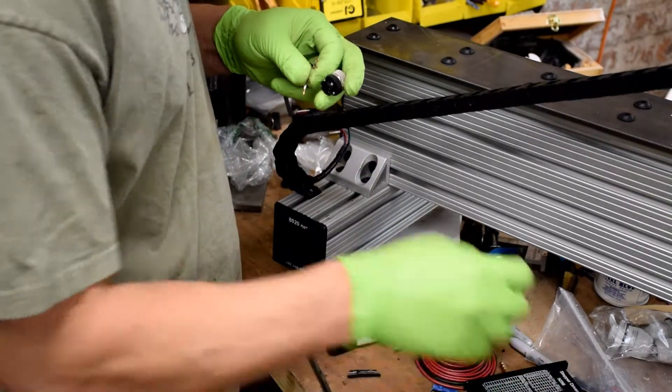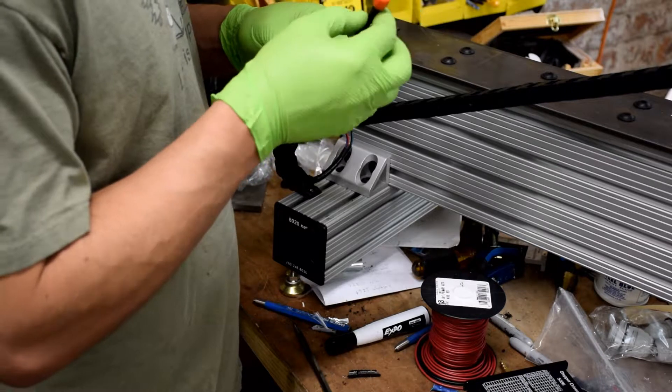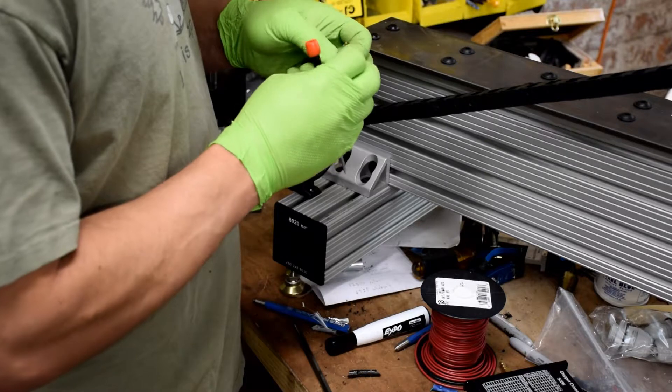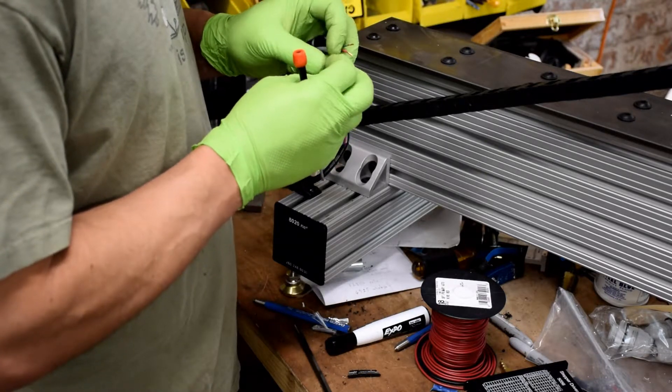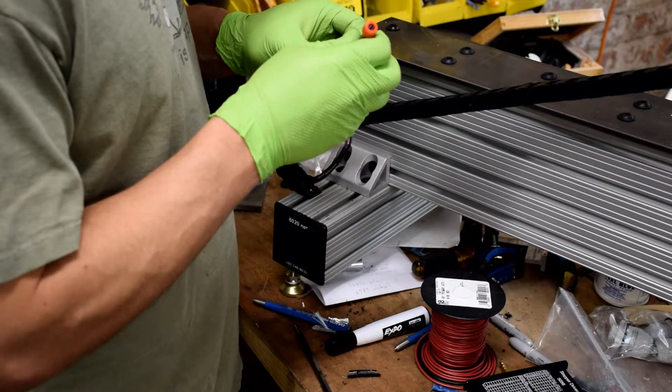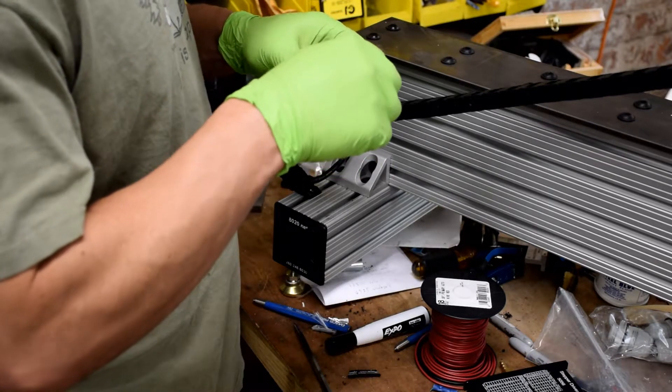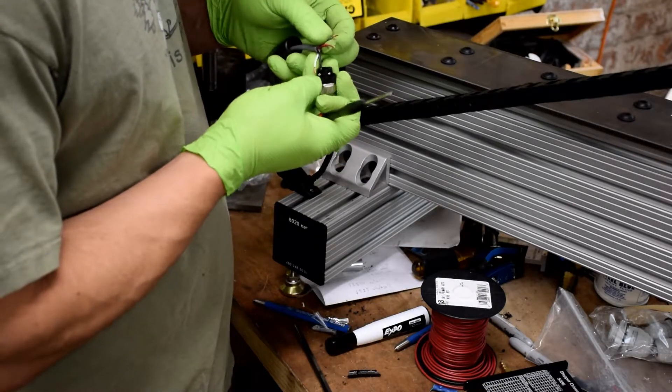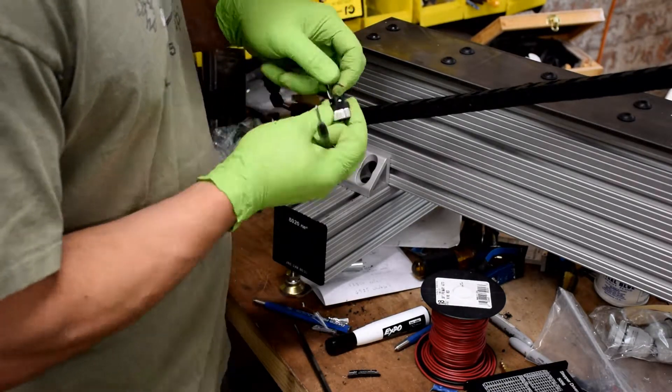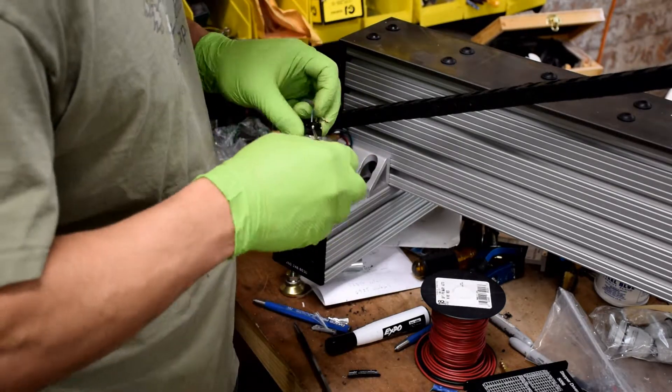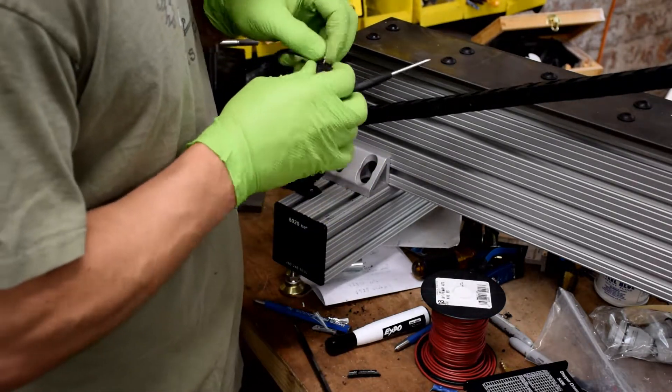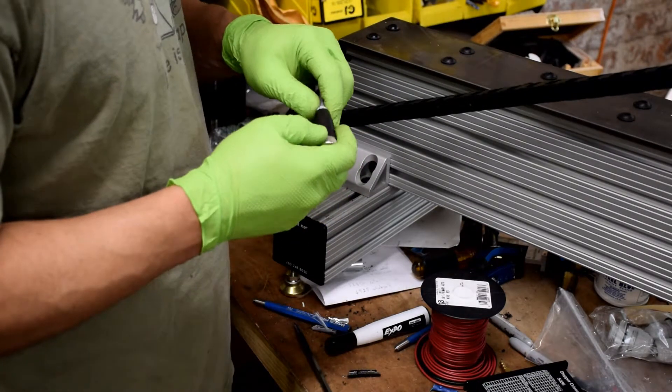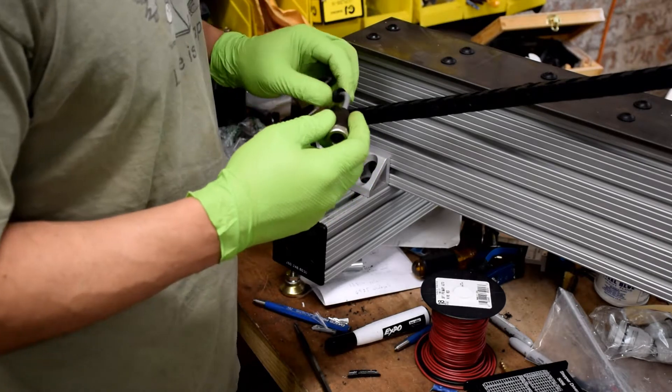There's numbers on here, and the wires are going to be wired up black into number one, green into number two, white into number three, and red into number four. Once you've got those wires terminated, screw the whole assembly back together.